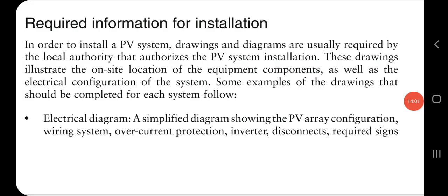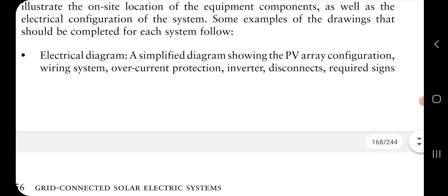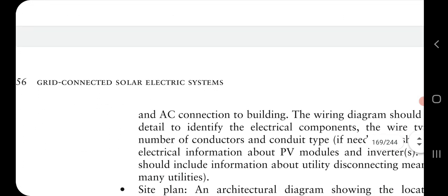The next is required information for the installation. When you are installing, proper drawing diagrams should be there, and they should be passed by the local authorities, and the drawing should illustrate the on-site location, equipment, everything. So the first thing that happens, the electrical drawing is very important. It will specify the PV array configuration, wiring system, overcurrent protection, inverter, disconnector, and the signs required for this.